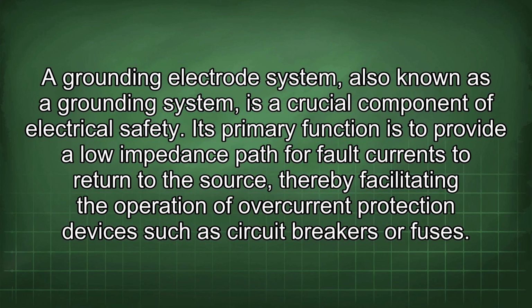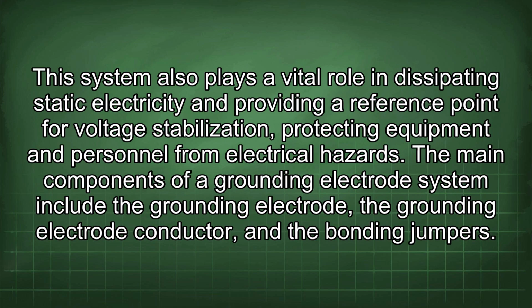A grounding electrode system, also known as a grounding system, is a crucial component of electrical safety. Its primary function is to provide a low impedance path for fault currents to return to the source, thereby facilitating the operation of overcurrent protection devices such as circuit breakers or fuses. This system also plays a vital role in dissipating static electricity and providing a reference point for voltage stabilization, protecting equipment and personnel from electrical hazards.